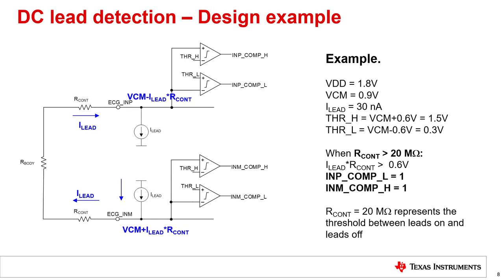A more realistic case might involve contact impedance at the INP and INM sides being of different values. Also, each electrode may have some DC offset, and this changes the exact value of contact resistance at which the leads-off thresholds are reached. The basic principles of operation outlined here can be extended to cover such cases.